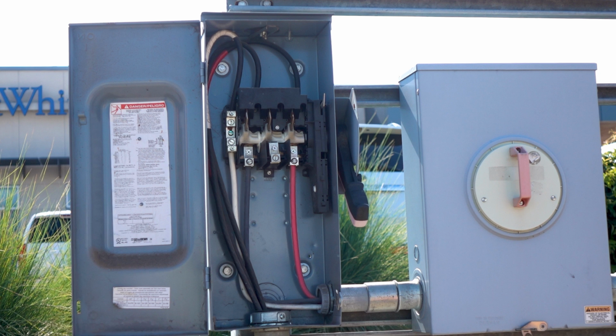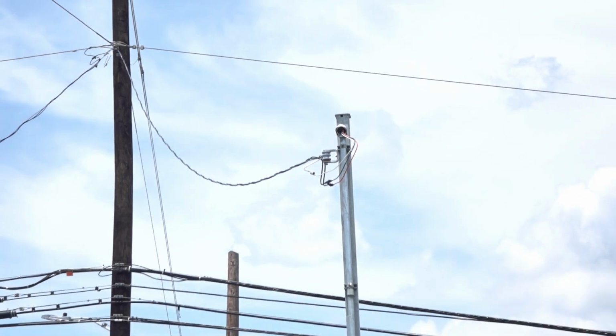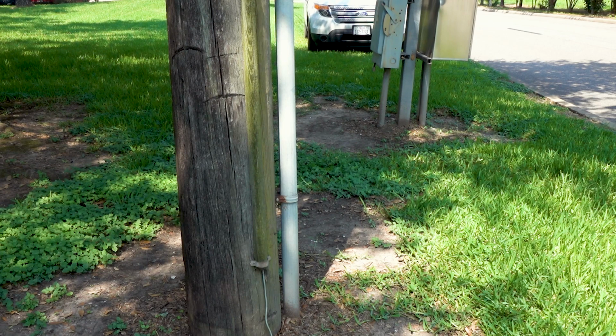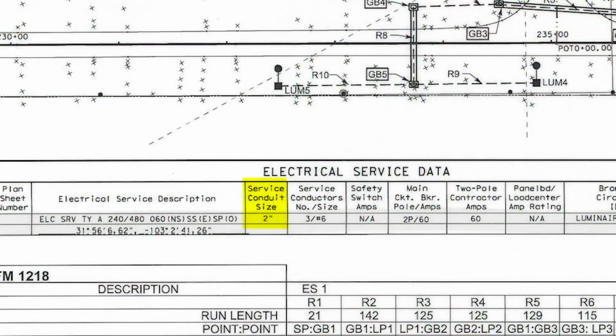This switch is different from a fused disconnect, which has fuses. The safety switch contains no fuses and is to be used only by the local utility company. The size of the service conduit, either overhead or underground, will be as called for by the engineer on the plans. The inspector must confirm that the correct size was installed.